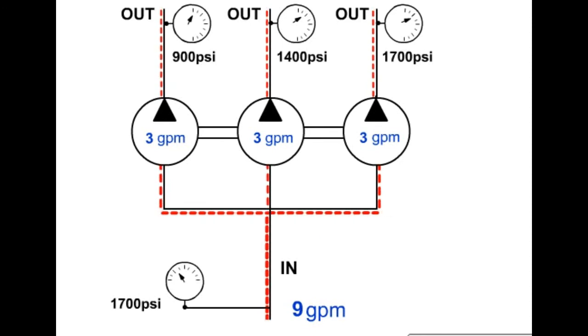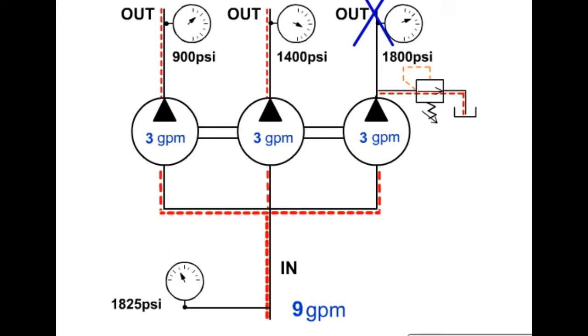If one of the output flows becomes blocked, all of the output flows will be blocked. Pressure intensifies in the circuit that is initially blocked. A relief valve placed in the circuit downstream of a proportional flow divider will prevent pressure intensification.